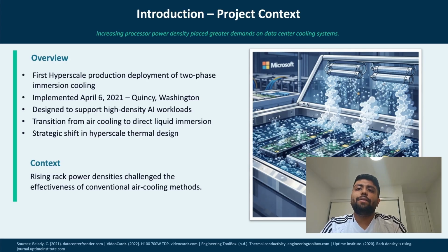This design represents a shift away from traditional air-based cooling systems. Instead of pushing air across heat sinks and through server racks, the cooling medium makes contact with the hardware itself. This transition was significant because rack level power densities have steadily increased over the past decades. As processor performance increases and workloads become more compute intensive, traditional air cooling systems become less effective at removing concentrated heat loads. Rather than continuing to incrementally improve air cooling, Microsoft explored an alternative approach that could support higher density compute environments more efficiently.